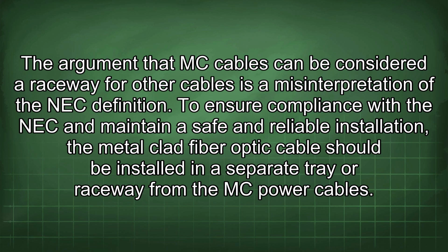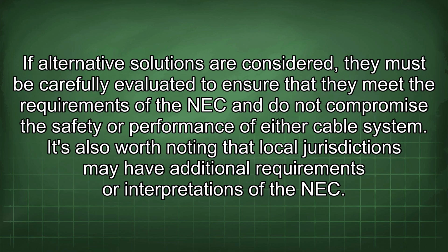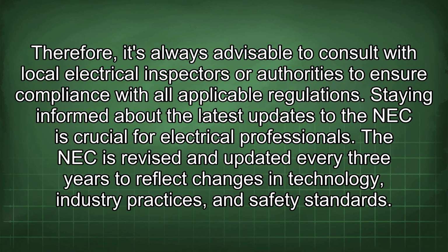To ensure compliance with the NEC and maintain a safe and reliable installation, the metal-clad fiber optic cable should be installed in a separate tray or raceway from the MC power cables. If alternative solutions are considered, they must be carefully evaluated to ensure that they meet the requirements of the NEC and do not compromise the safety or performance of either cable system. It's also worth noting that local jurisdictions may have additional requirements or interpretations of the NEC. Therefore, it's always advisable to consult with local electrical inspectors or authorities to ensure compliance with all applicable regulations.